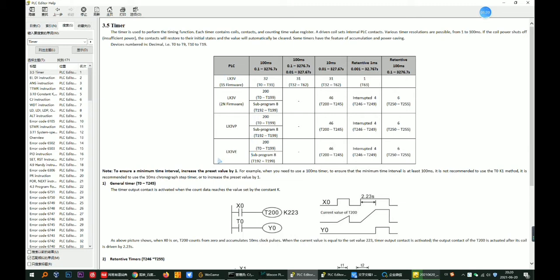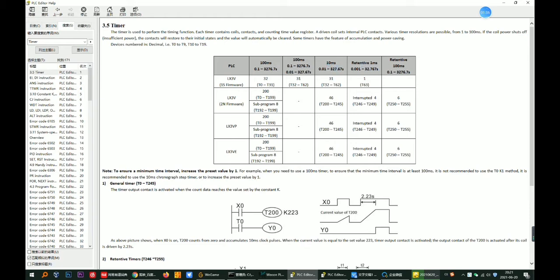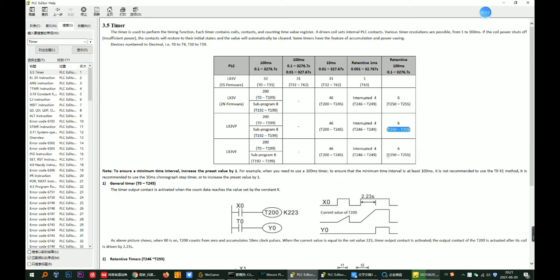In the LX3V series, T0 to T199 is 100 millisecond time, and T200 to T245 is 10 millisecond time, and T246 to T249 is 1 millisecond cumulative time, and T250 to T255 is 100 millisecond cumulative time.